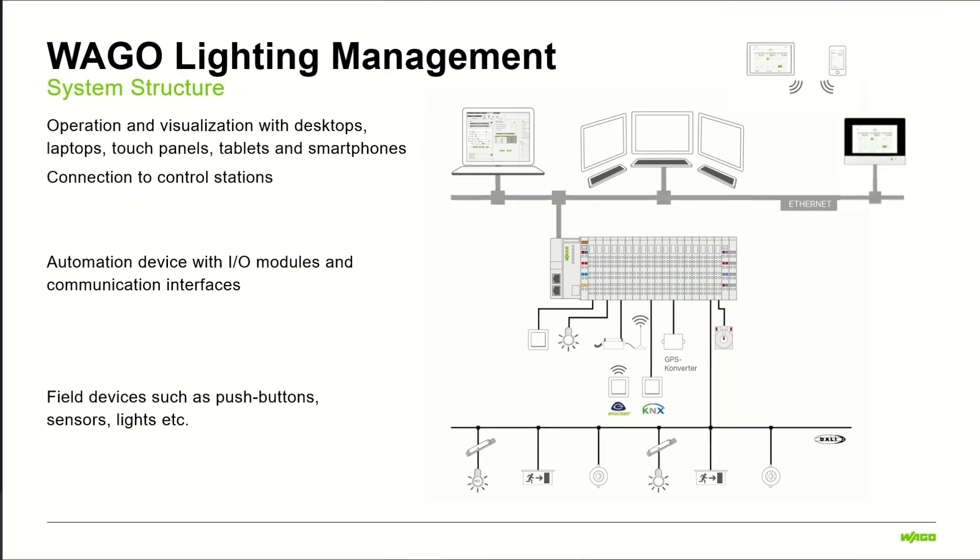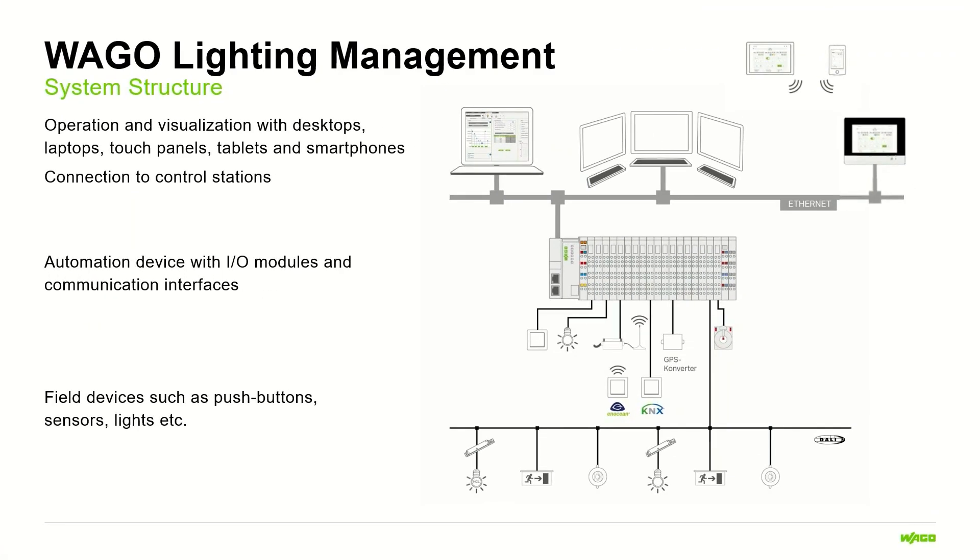Via IO modules or communication interfaces, several sensors or actuators like luminaires could be connected to the system. Luminaires and sensors, for example via a DALI line, luminaires via digital outputs, push buttons via digital inputs or also EnOcean, a wireless technology or also KNX.